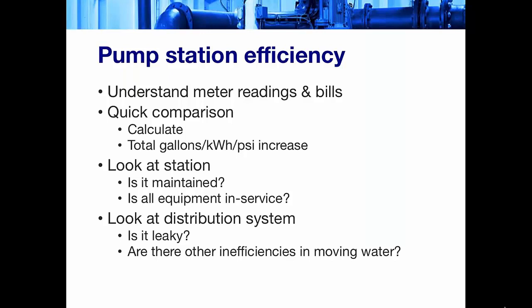Another thing is that pump stations often have multiple pumps for redundancy. If you have some of the equipment components that are out of service, or if some of the control systems have been bypassed, that's a good indication that the pump station is not being operated as it was designed to be operated. So if it's being operated outside of the design, that's a reasonable indication that it might not be a very efficient pumping station. And finally, what we can do is look at the distribution system. Is the distribution system that the pump station is supplying a leaky distribution system?